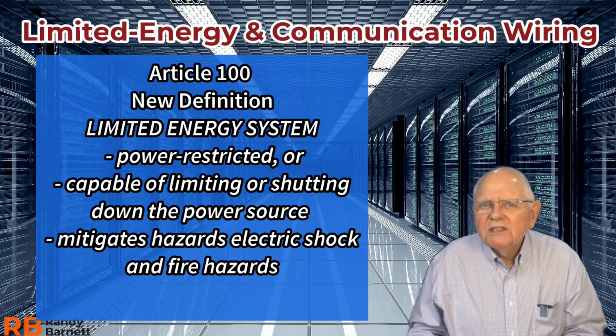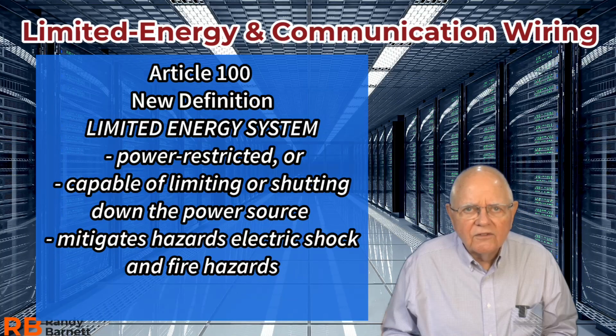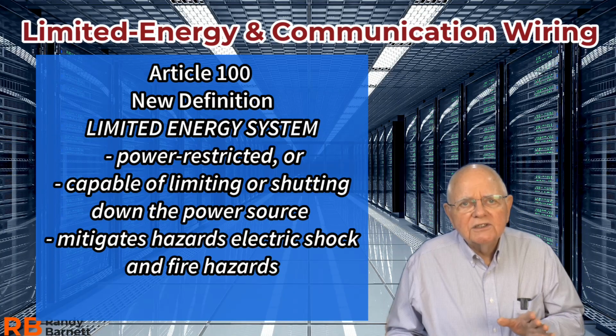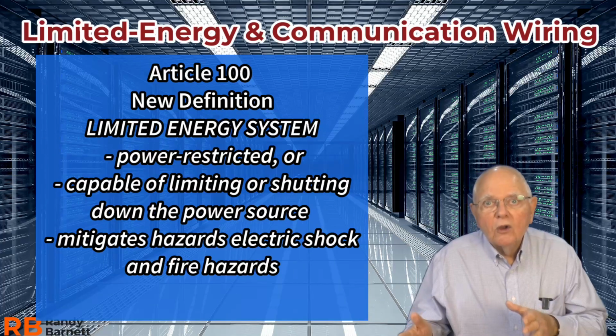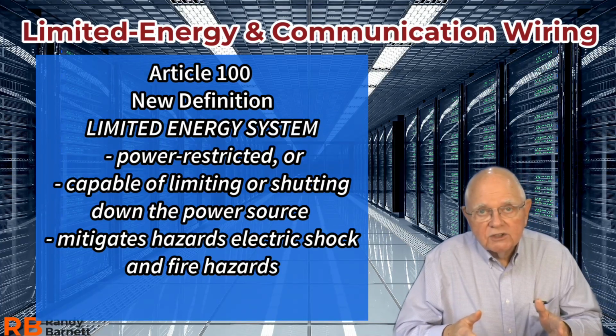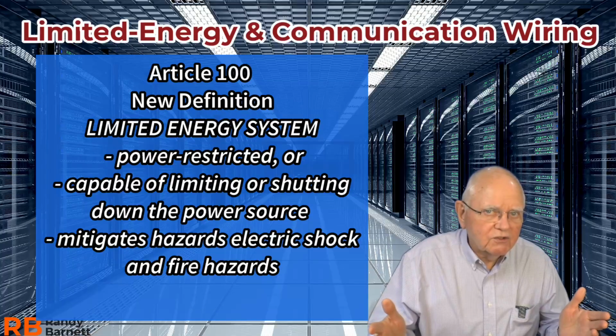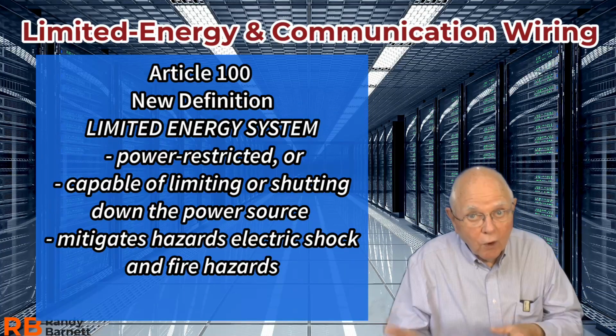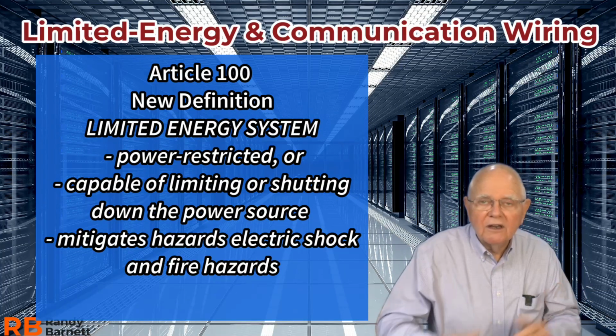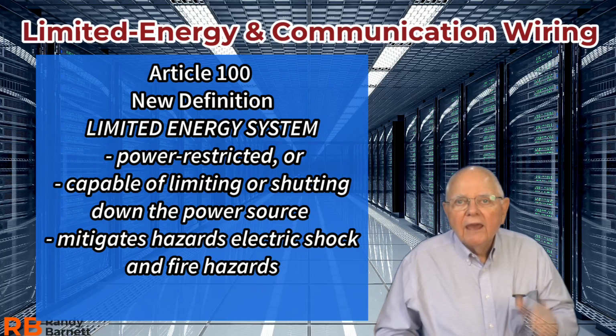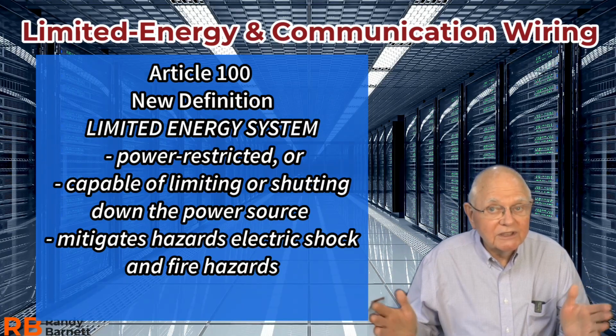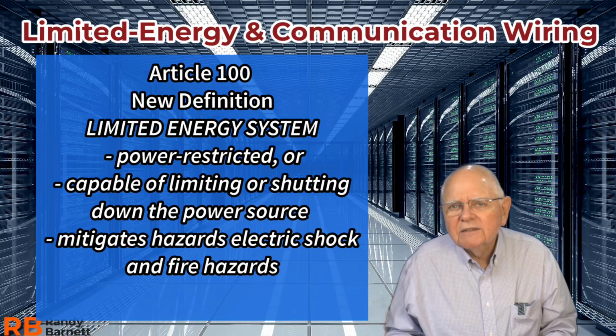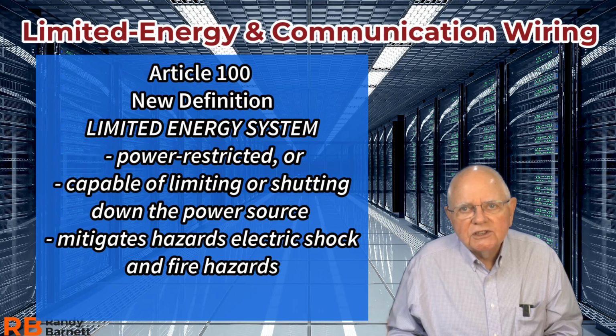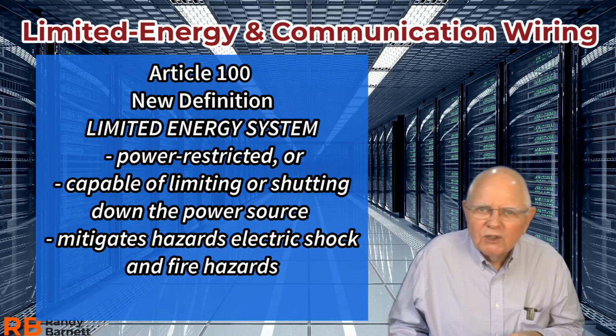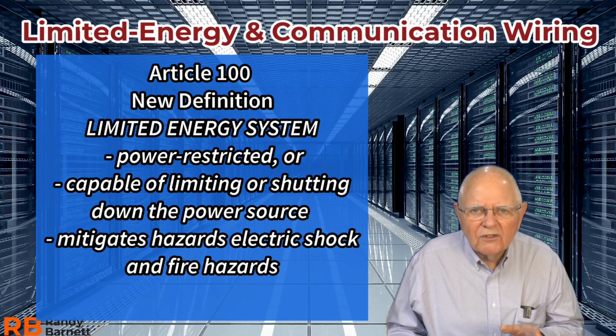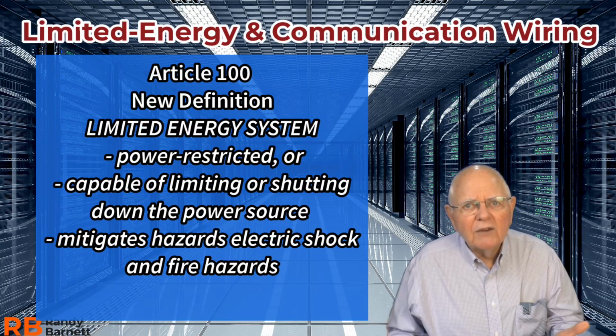There's a good informational note at the bottom of that definition that's going to tell you what some typical limited energy systems are. Class 2 and Class 3 systems. Class 4, which first appeared in the last edition of the code, and power limited fire alarm systems. Those are certainly power restricted, and our communication systems as well. How do they do all this? We'll talk more about it as we get into it, but through inherent design within the equipment.